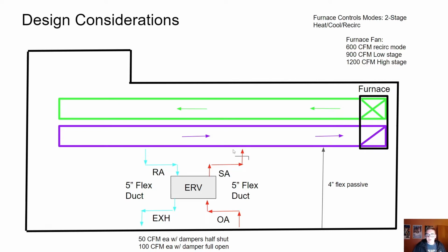So I also purposely have it set up this way such that if I set the dampers at the exact same position, because the supply side is closer to the furnace blower, the supply side is always going to be bringing in a little more air than the exhaust side. So I'm going to have it naturally always slightly positively pressurized, and we'll go into some of the benefits of that, but you want to be as close to equal airflow as possible.